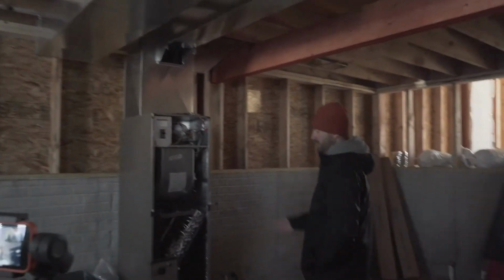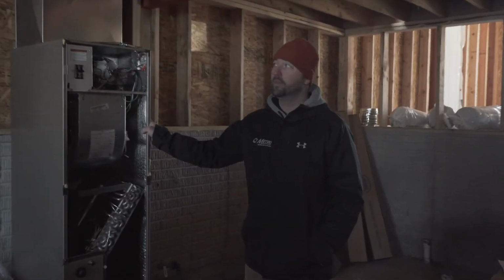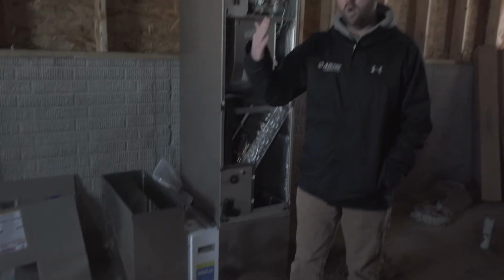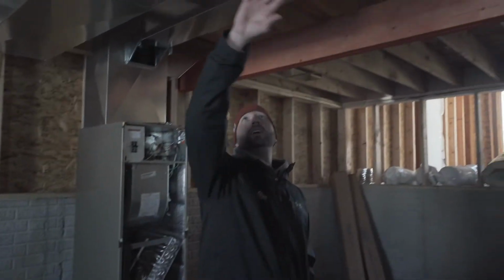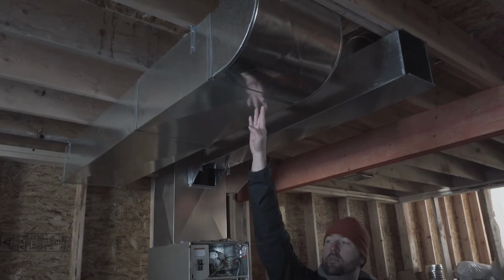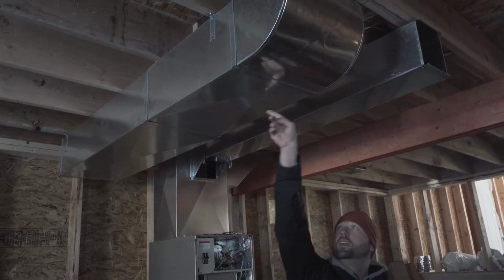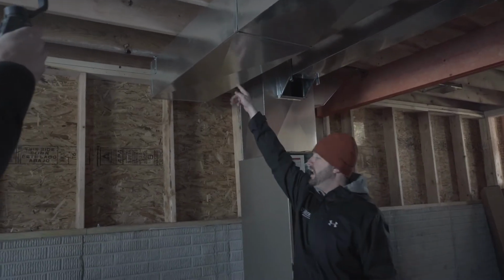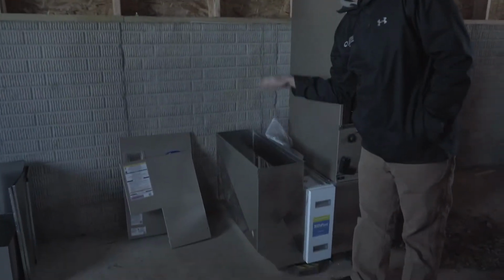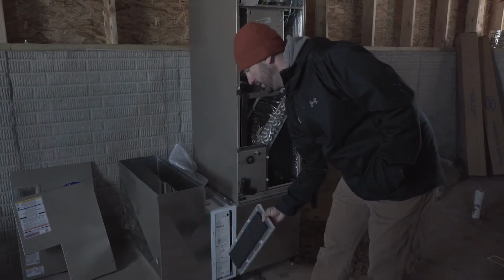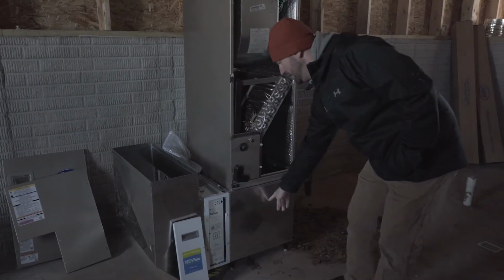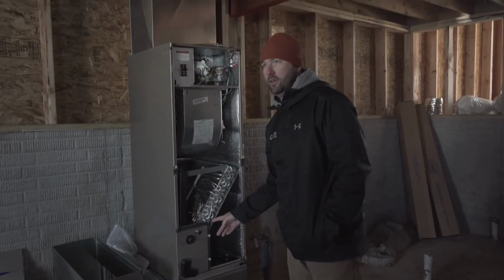Right now, you can see you have the furnace set, and they're starting on the return air drop. So when I said on the walls where they have a register or a grill, where the air is getting sucked in, it goes into this ductwork here, and then it comes in this direction, and then down. This is called the return air drop, and then it goes through a filter here, and then it goes down and up into the furnace.